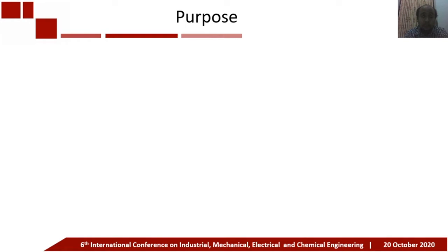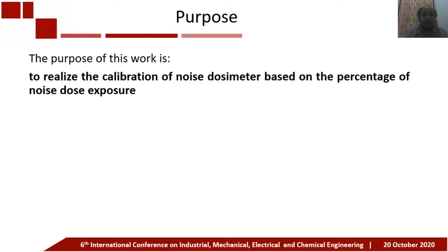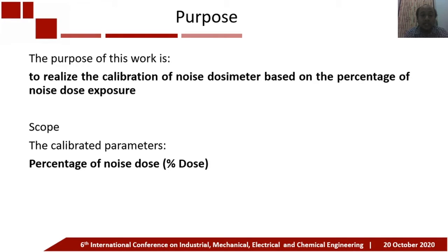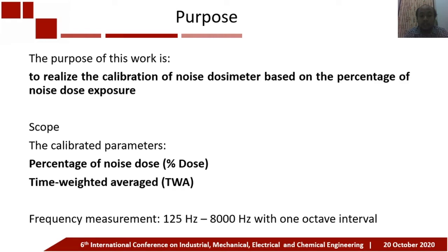So, this encourages us to conduct the research with the purpose of realizing the calibration of noise dosimeter based on the percentage of noise dose exposure, where the scope of this research is limited to the parameters that consist of the percentage of noise dose or percent dose and time weighted average, TWA, as the optional parameter, with the frequency range of measurement starting from 125 Hz to 8 kHz with 1 octave interval.